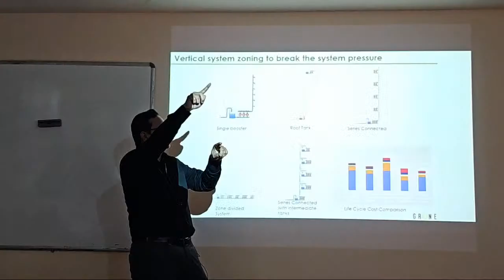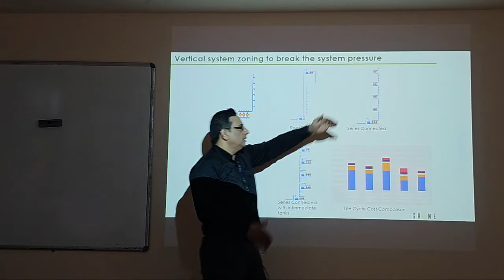When I show a stacking of those service floors and rooms, I would have a series of multiple pumping stages happening. One series takes care of the various floors, and the next set takes care of the next floors. This is done in Burj Khalifa. A building which is 828 meters tall cannot be done with one single riser. It will be done with multiple ways of managing it. So I would say a tall building of more than 300, 350 meters will be done like that. A residential building will be done like this. Or it can be done with smaller floors, a second set of floors, and the next set of floors with various stacks. It consumes more space but is effectively able to manage.